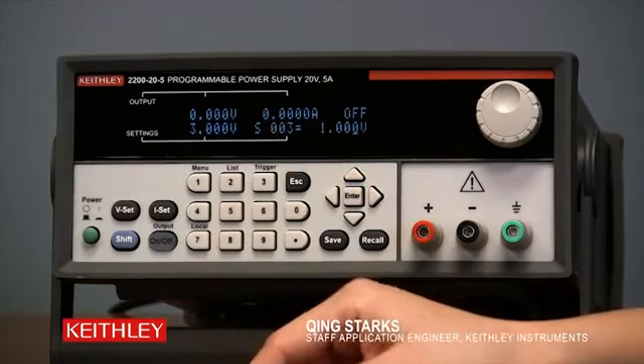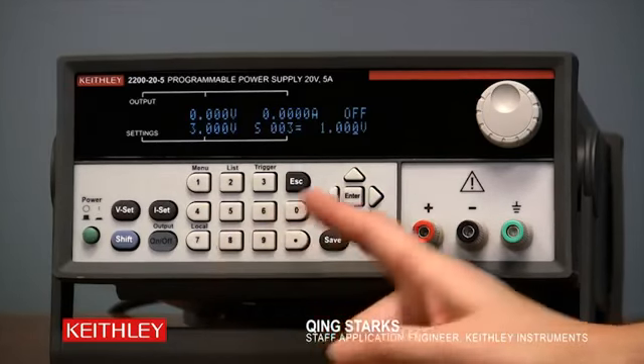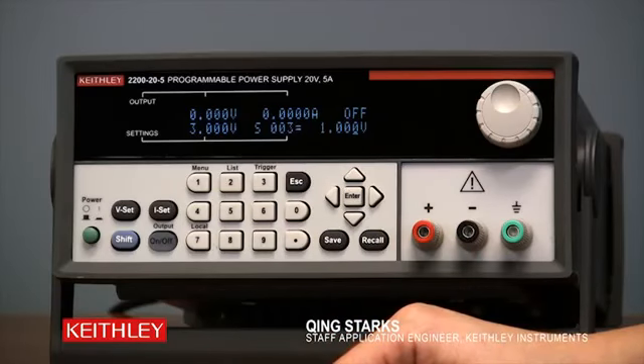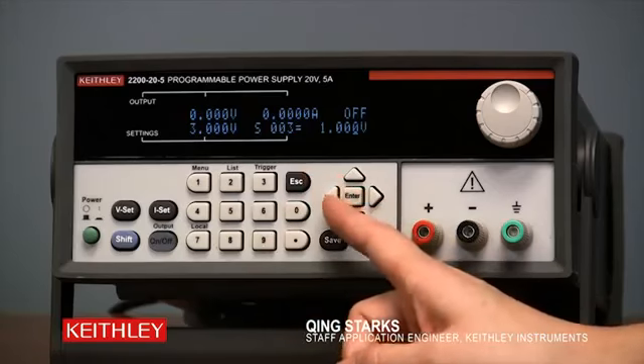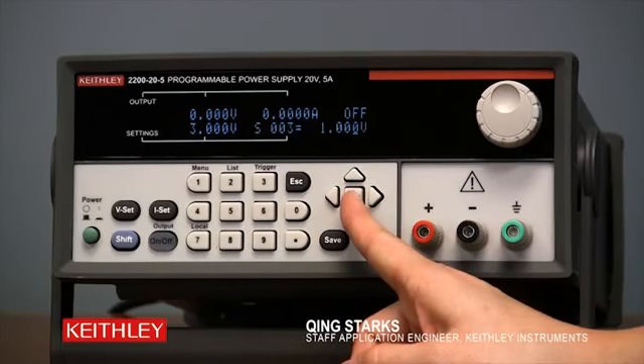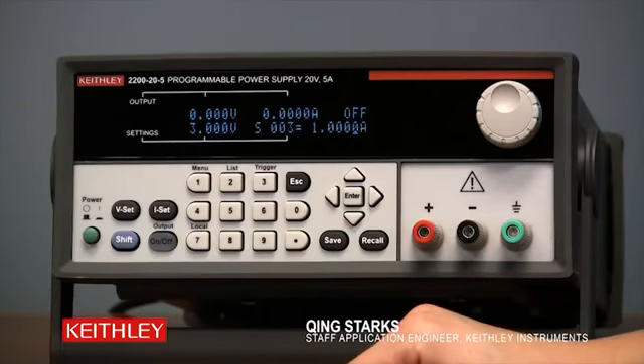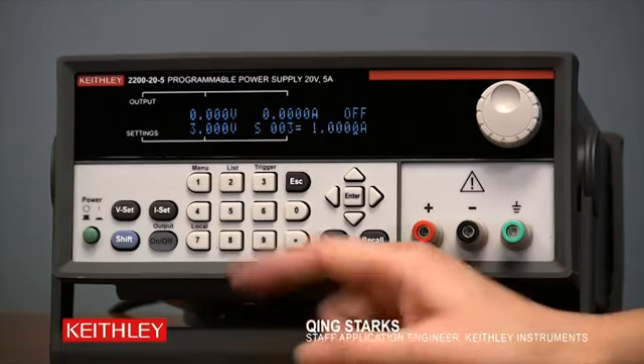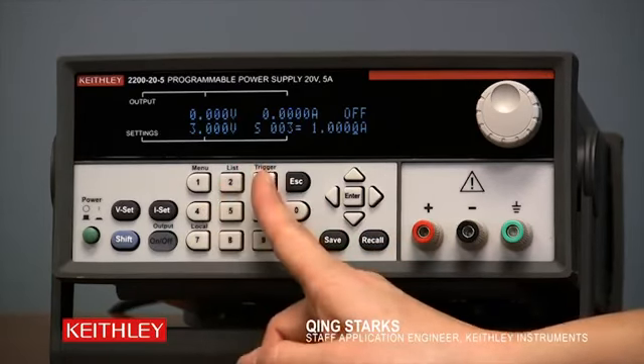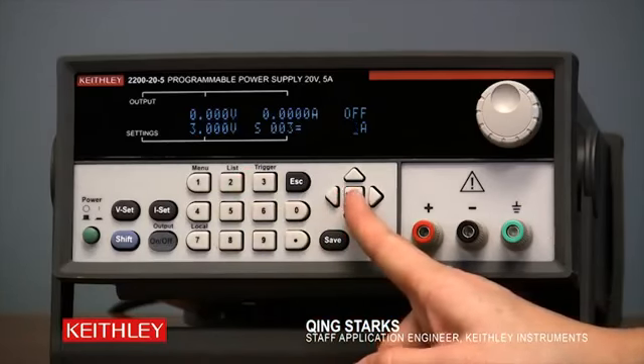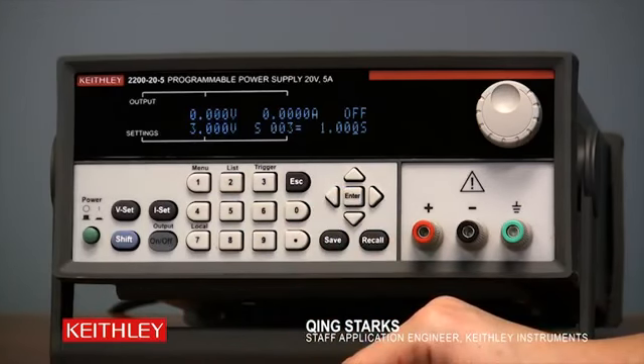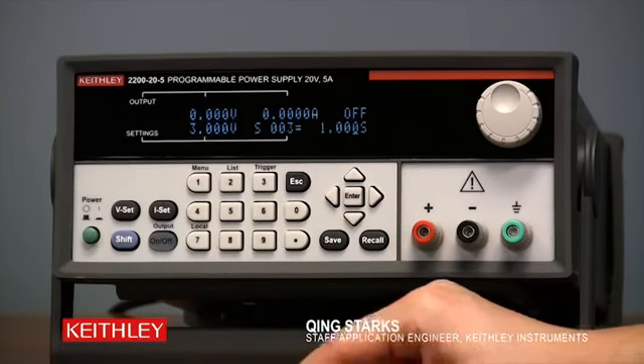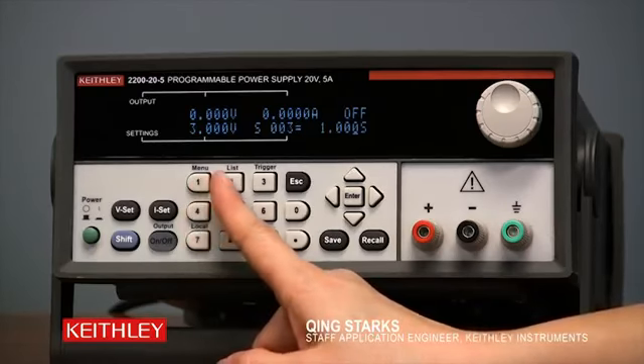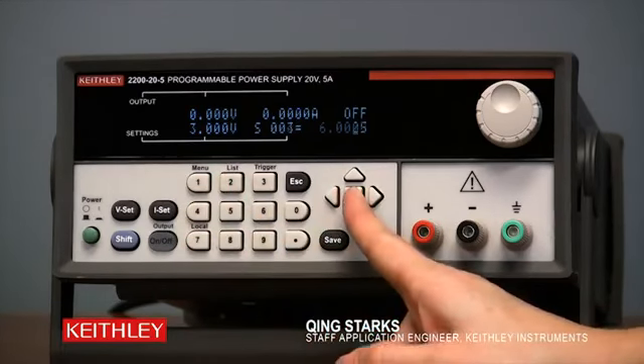As you can see, it's S003, and it's ready for you to accept the voltage setting. Right now it's set to 1 volt, and we're happy with that. We can just press Enter. And the current limit is at 1 amp. If you would like to change that, you can change that to, say, 3 amps and press Enter. And the duration is 1 second. Again, we can change that to 2 seconds and press Enter.